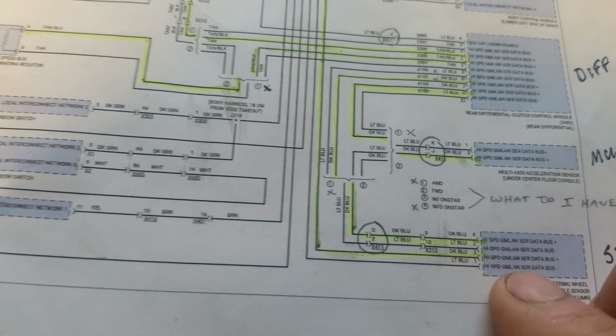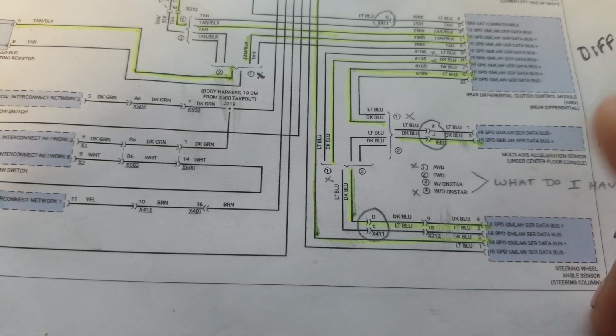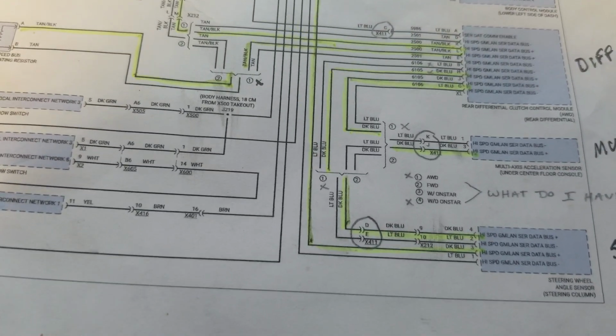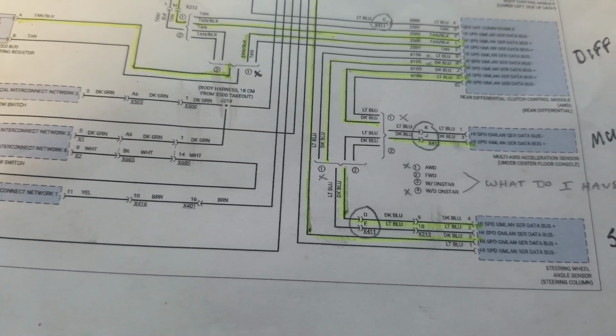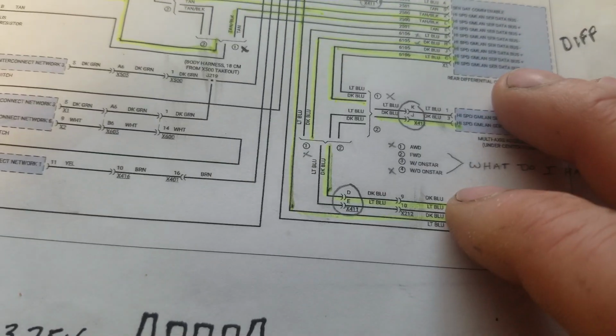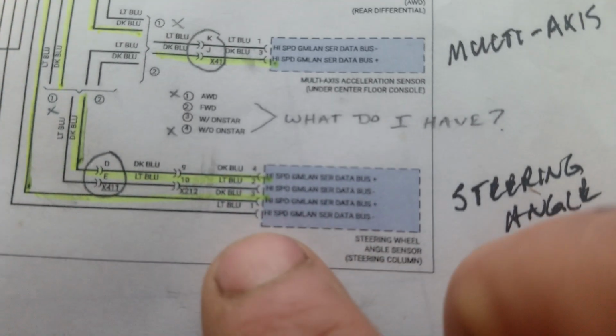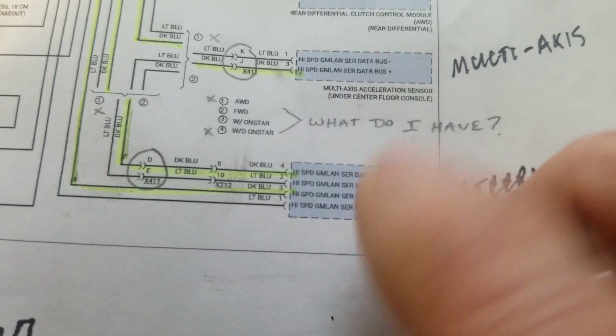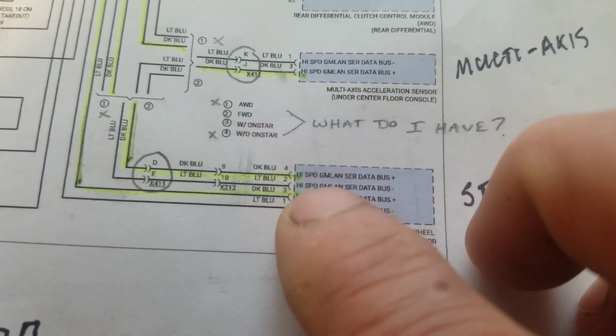And then we would have to tie into... What I'm trying to say is, the problem with disconnecting these modules is that you have to remember that if you disconnect its connector, and if you look on the diagram, you'll see the dotted line around the module. That means it's a partial view of all the wiring that goes into it.